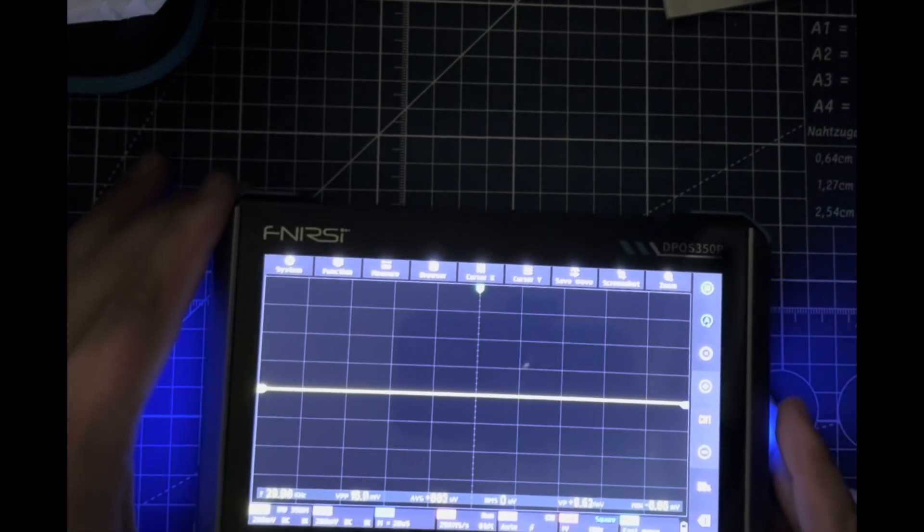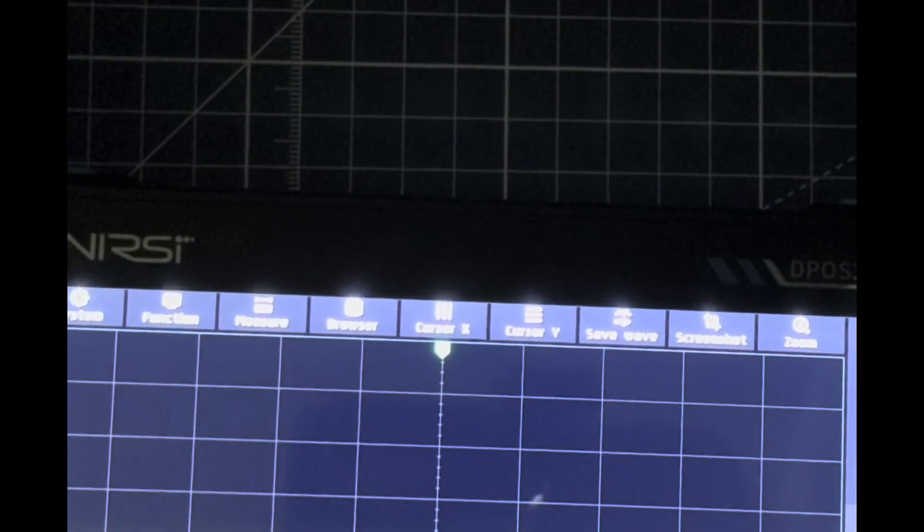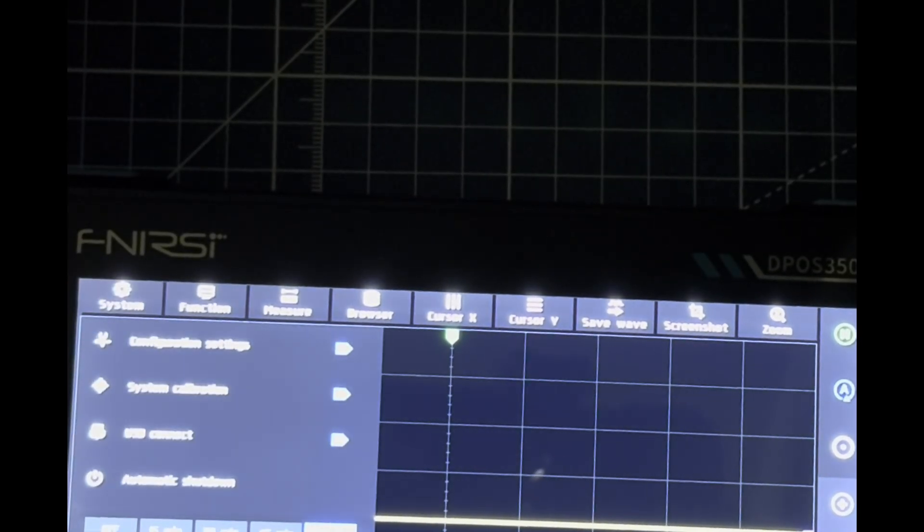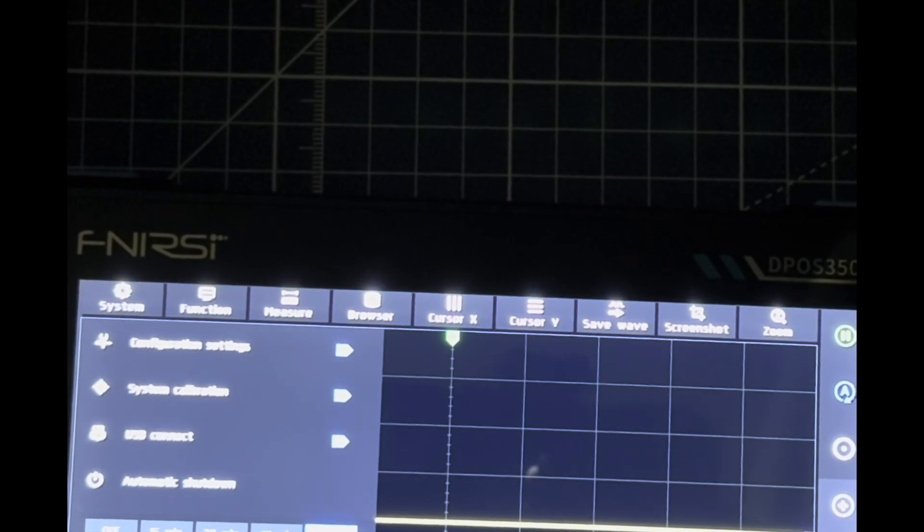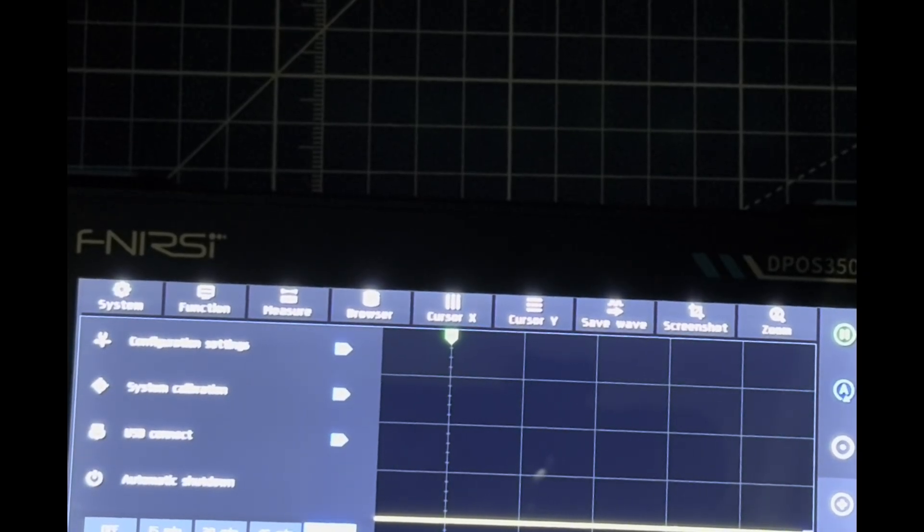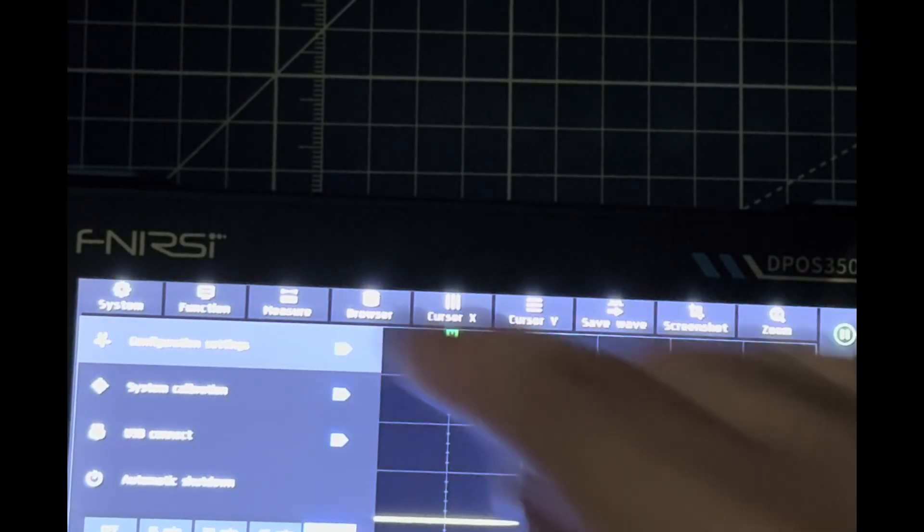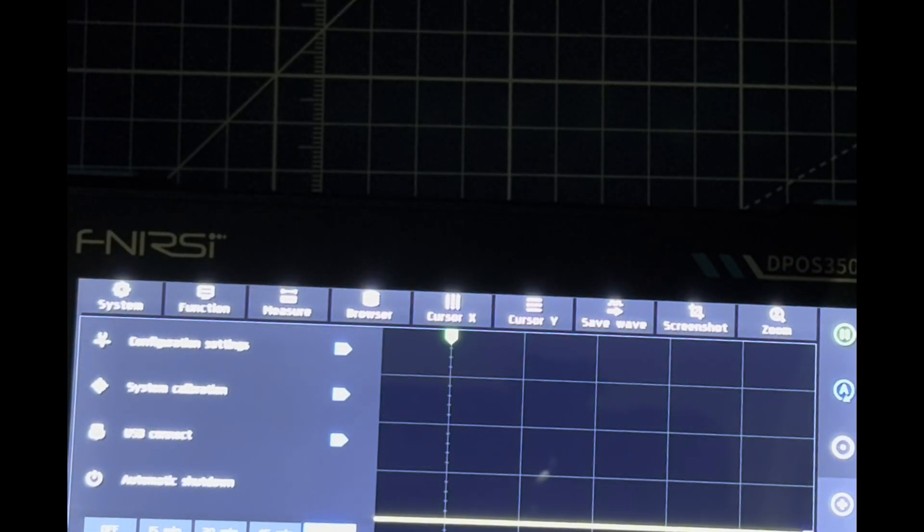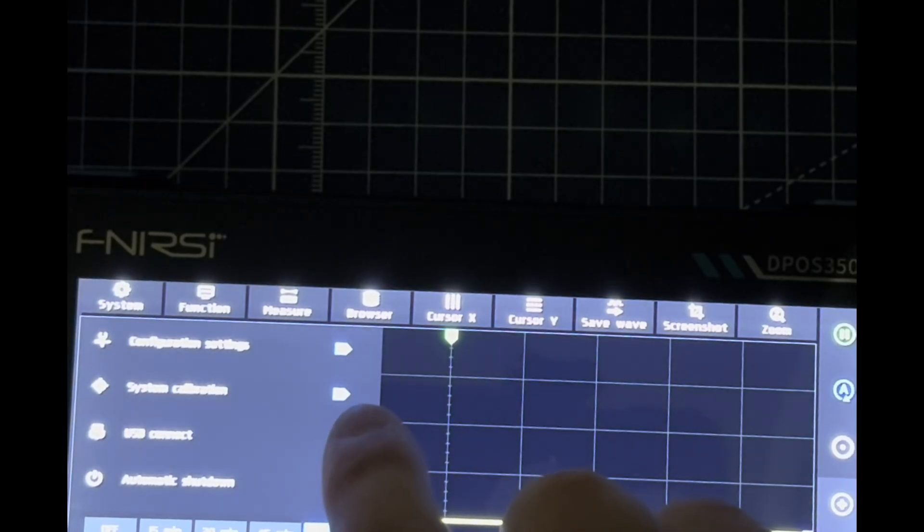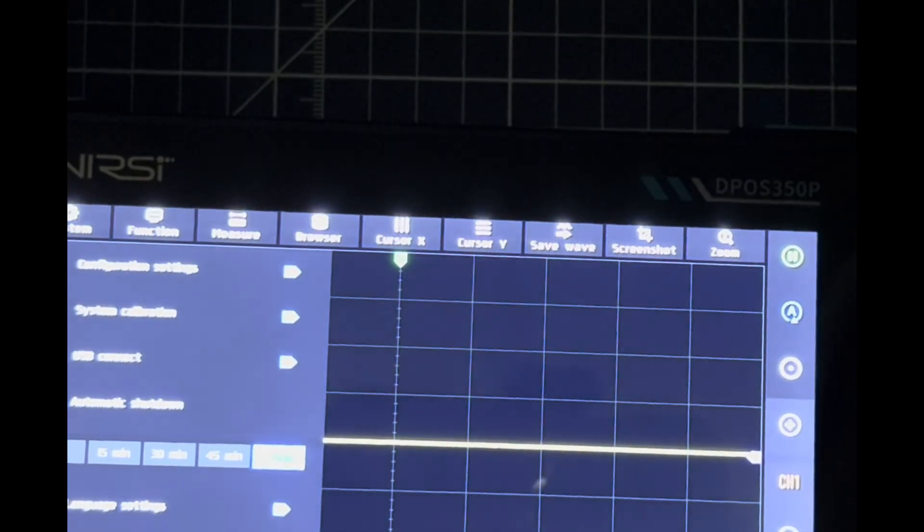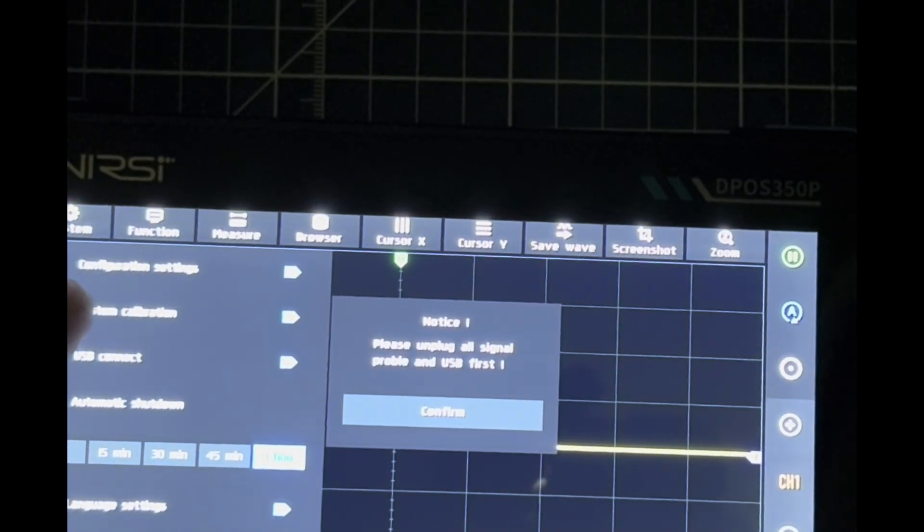This just takes the display away and brings it back with your battery indicator right there. At the top we have our system where we can configure, calibrate, USB connect, and configuration settings. Very simple. We can save or read configurations, connect to a monitor as you can see, and calibration takes about 40 seconds.